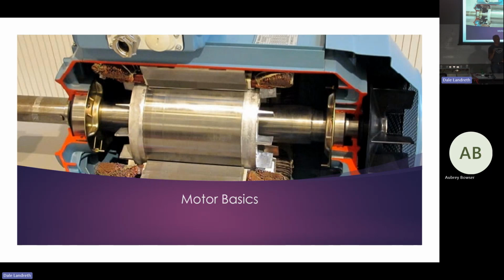So we go out, and again, we're not just talking about a big motor - we can use this motor right here as an example of what we're talking about. So if this motor gets too hot and starts breaking down the lacquer, breaking down the insulation, how do we find that? A mega ohm test. So what does a mega ohm test do?